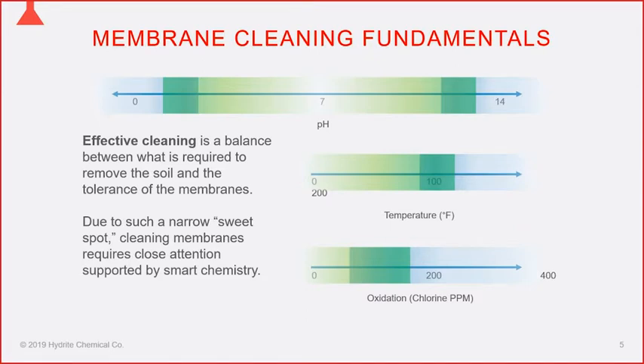When using chemicals such as chlorine or other oxidizers, concentrations have to be monitored to ensure they're in the effective range. If they're too high they can damage the membranes; if they get used up during cleaning, incremental additions must be made to ensure cleaning effectiveness. You can't just hit the start button on the CIP and walk away.